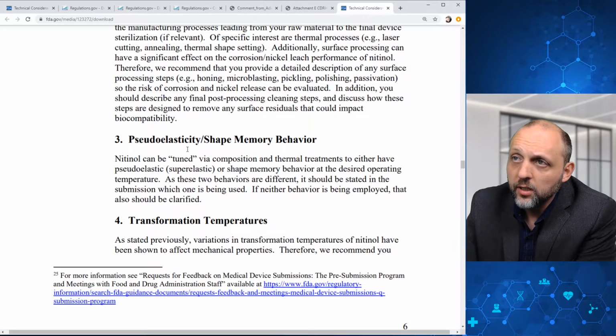And then in terms of the pseudoelasticity or shape memory behavior, here FDA again comments on the fact that nitinol can be tuned via composition and thermal treatments. And it should be stated in the submission which of these properties, the pseudoelastic or shape memory behavior, are being used. If neither behavior is being employed, that should also be clarified.